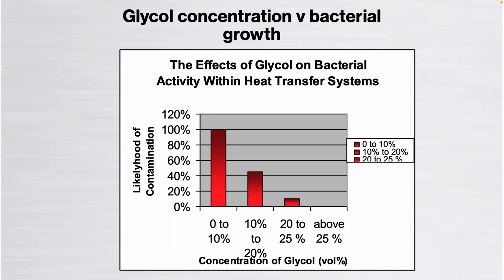So you may have a chilled water system or even a heating system, and you think, where's my glycol gone? I've lost it. Well, it's a combination of leaks and a combination of bug problems. You think you've got air in the system, you can't get rid of it. You're losing glycol. You could actually find that you've got glycolic acid being produced. The bugs are now eating it, producing glycolic acid. And as I say, what do we have with acid or acidic conditions, sub 7? We start having problems with increased corrosion.